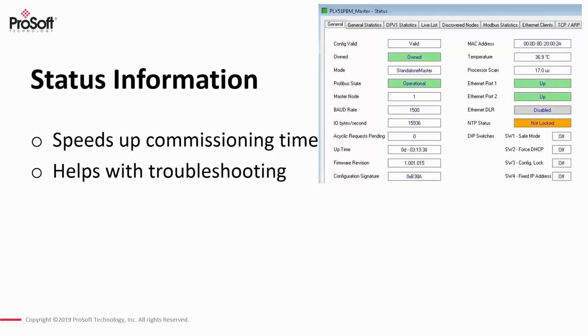As far as the module itself, there's quite a bit of status information that's available through this PLX50 configuration utility. Through the config utility, you can go in and look at the status of an individual module. It's going to tell you everything from your MAC address, your status on your Ethernet ports, whether or not DLR is being used. And then there's a couple of dip switches on the module that, if you wanted to do something like a fixed IP address or lock out a configuration, you can set individually on the module itself.